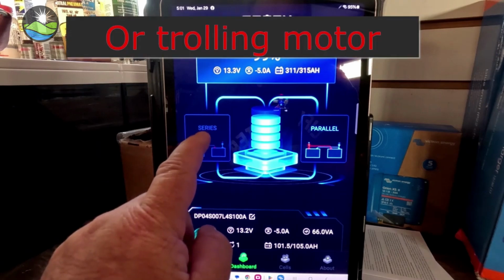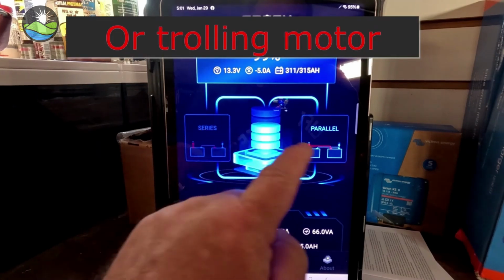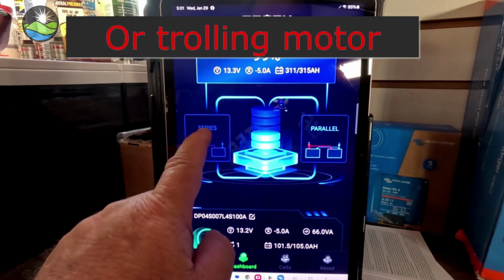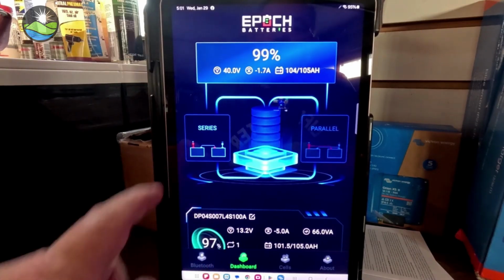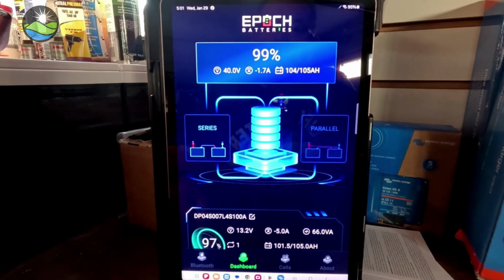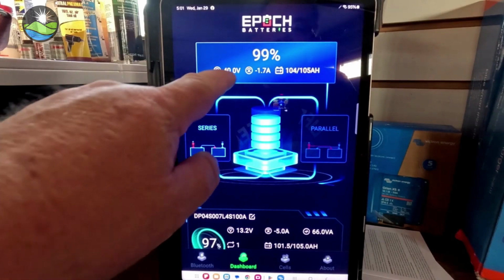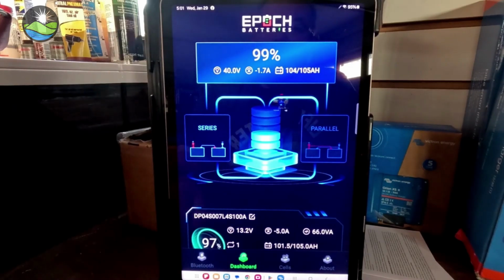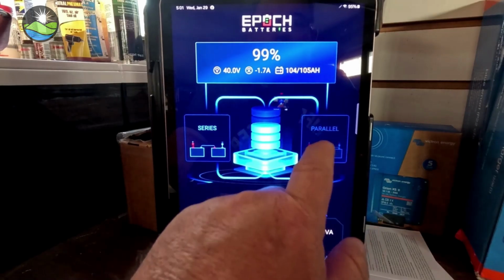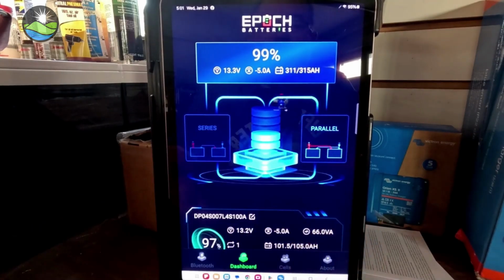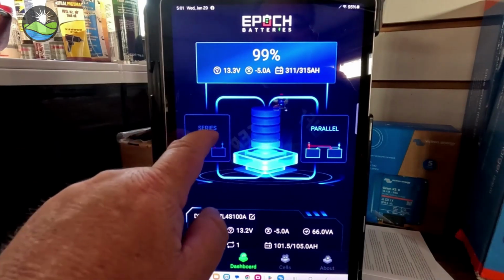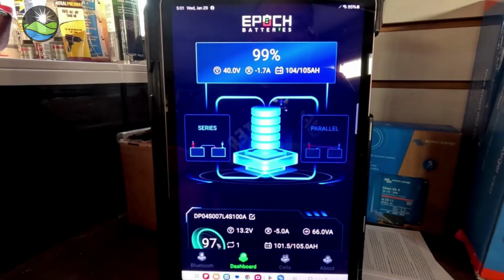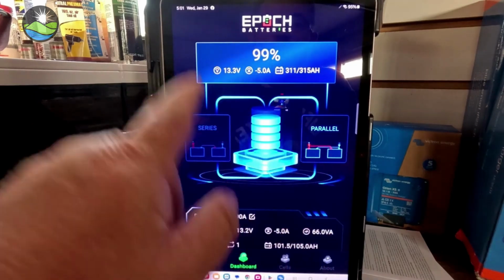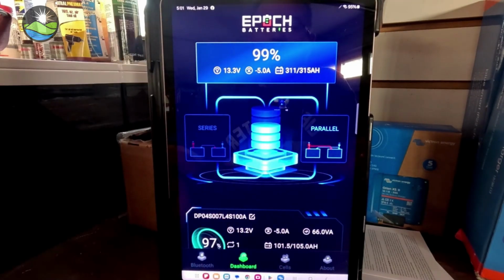Now if this was a golf cart and you had these wired in series, as you see it says parallel over here, if you had it wired in series, click that button and it will totalize it in a series fashion. So this would be your series voltage, and then it only shows 104 of 105 amp hours because that's how that works when you go in series versus parallel. Parallel, the amp hours are added, the voltage is not. Series, voltage is added, amp hours are not. Just very simple, but this is useful if you've got several batteries online to take a quick look.